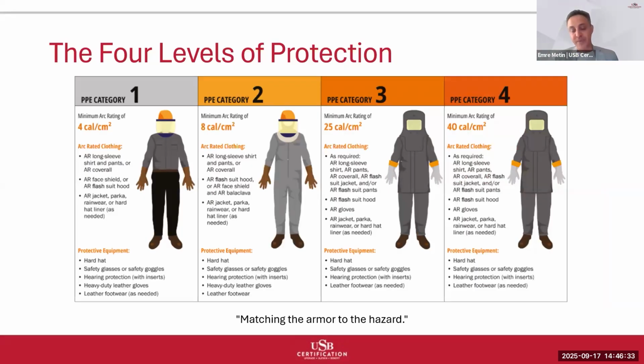Let me walk through the NFPA categories in detail because understanding these requirements is essential for proper implementation. Category 1, 4 calorie per square centimeter minimum. Arc-rated long sleeve shirt and pants or arc-rated coverall. Arc-rated face shield or arc flash suit hood. Arc-rated jacket, parka, rainwear, or hard hat liner as needed. Protective equipment: hard hat, safety glasses or goggles, hearing protection, heavy-duty leather gloves, leather footwear. This represents the minimum level of arc-rated protection for low energy exposures.